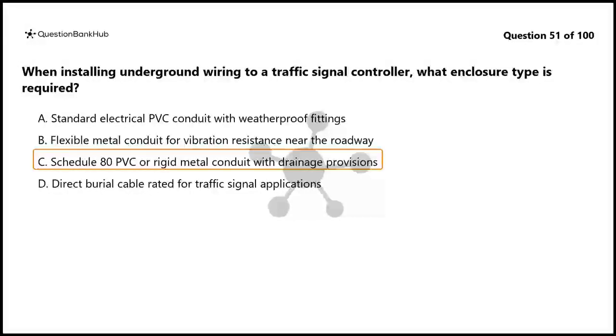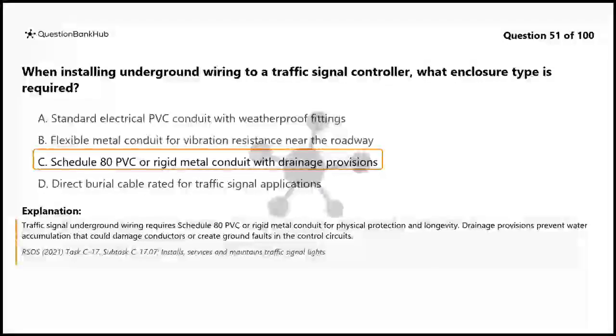The correct answer is C. Schedule 80 PVC or rigid metal conduit with drainage provisions. Traffic signal underground wiring requires Schedule 80 PVC or rigid metal conduit for physical protection and longevity. Drainage provisions prevent water accumulation that could damage conductors or create ground faults in the control circuits.